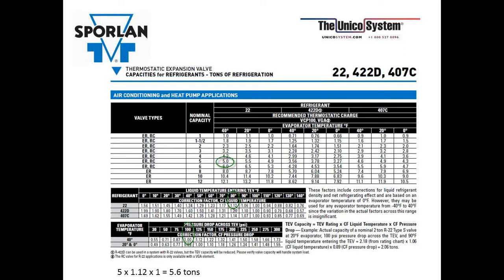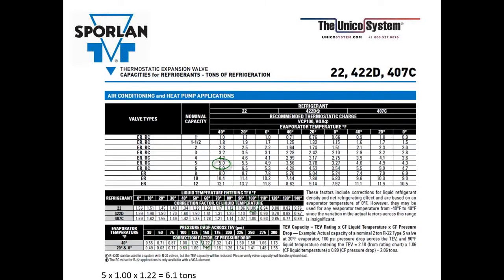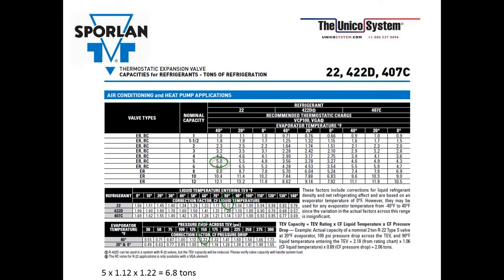So just by changing the temperature of the liquid, you've increased the capacity of the valve just a little over ½ ton. And here we changed just the pressure drop across the port from 100 to 150, and now the correction factor there is 1.22, so we've increased it by 22%. If you use the same multiplication of the correction factors, now we've got a 6.1 ton valve. And then if you take it one step further, we change both the temperature of the liquid and the pressure across the port, multiply it all out, and now that's a 6.8-ton valve. So you can see just by changing the parameters that you're using, your nominal capacity valve's actual capacity can be either higher or lower, depending on the operation.